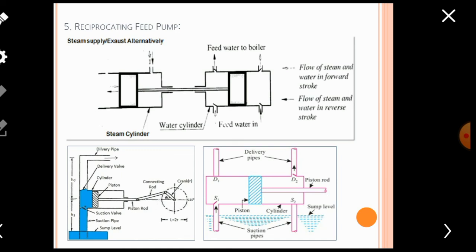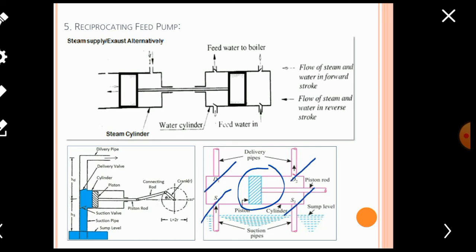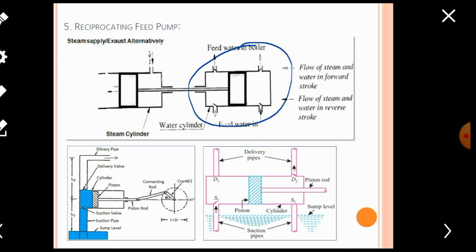On the right-hand side there is one more type of pump used especially in medium or high-pressure boilers — the double-acting reciprocating pump. Double-acting means that on both sides of the piston, suction and delivery can happen alternately by the movement of the piston. This is the same principle as seen in the water cylinder of the steam feed pump.